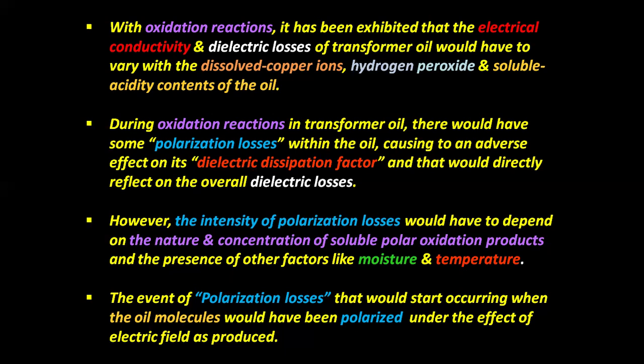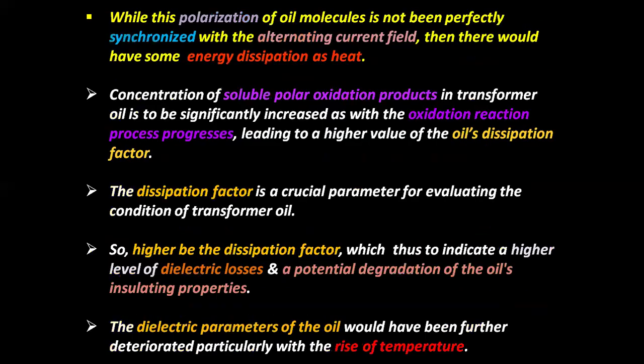Polarization losses start occurring when the oil molecules are polarized under the effect of the electric field produced. When this polarization of oil molecules is not perfectly synchronized with the alternating current field, there is some energy dissipation as heat. The concentration of soluble polar oxidation products in transformer oil increases significantly as the oxidation reaction process progresses, leading to a higher value of the oil's dissipation factor.